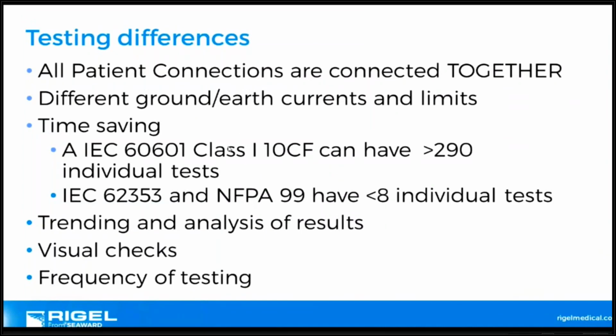But what I've stressed in videos that you can find on YouTube is that if you're testing to 60601 and you're doing something like an ECG machine, which is a class 1 type CF device, it can take up to 8 minutes or over 8 minutes to test because you're doing over 290 individual tests. If you test to 62353 or NFPA 99, you typically have less than 8 individual tests, so it takes about 40 seconds. So there's a massive time saver in how you do your testing.